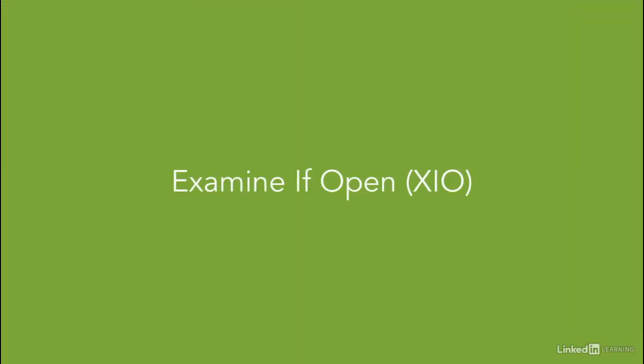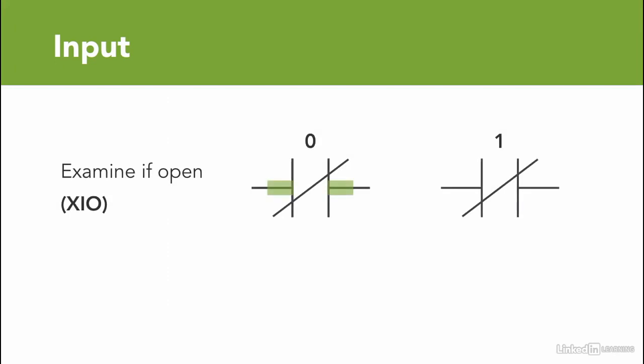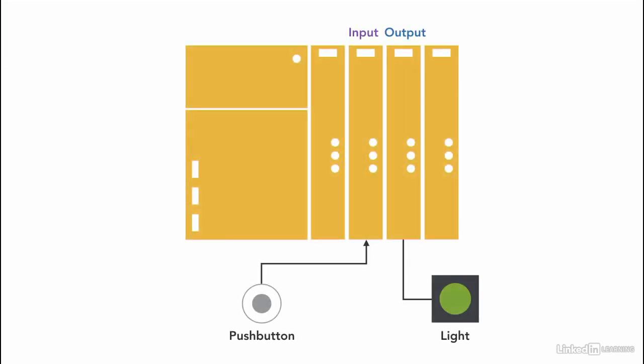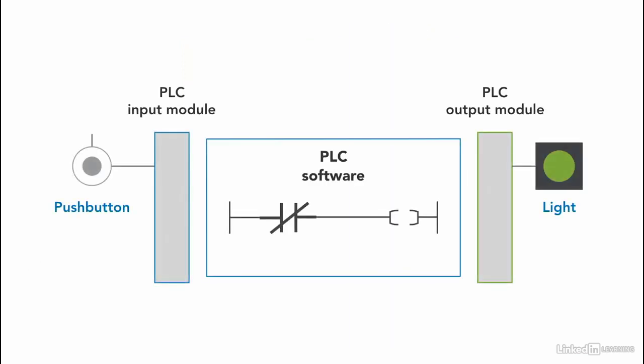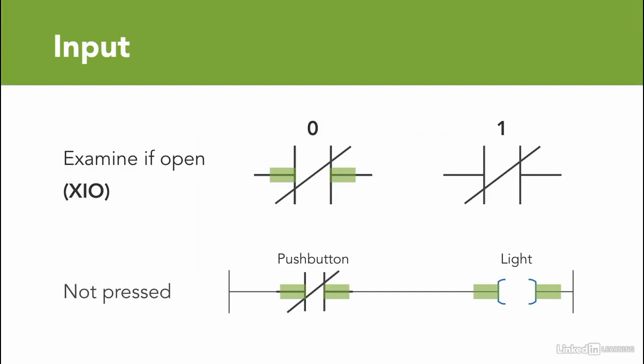Now let's use the Examine If Open instruction. XIO instruction acts the opposite way — it is activated when the logic state is 0, and not activated when the logic state is 1. Taking the same example with the same push button and light connection, but only changing the PLC ladder logic program to use XIO instruction: when the push button is not pressed, the logic state is 0, and since we are using XIO instruction, it's activated and the light will be on.